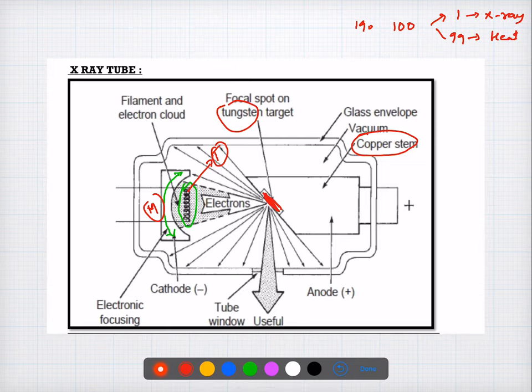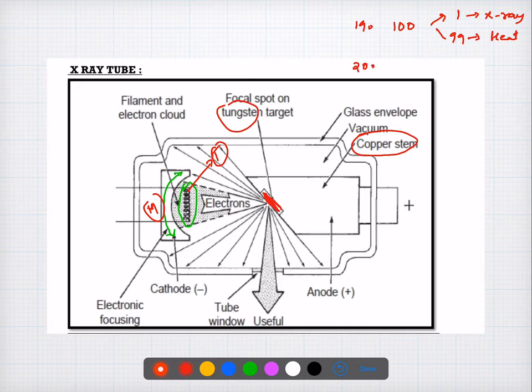Question twenty: the penetration power of an x-ray is determined by KVP. The answer is C. Question twenty-one: the most common cause for x-ray tube failure is the loss or failure of the filament.